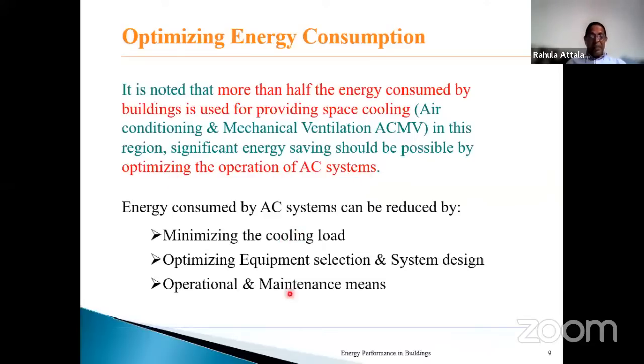Well, these three are the key important strategies to optimize the operation of the air conditioning systems. First, energy consumed by the air conditioning systems, or energy performance, can be handled or reduced by first minimizing the cooling load. So the first strategy, let us see, can be done at the design stage.